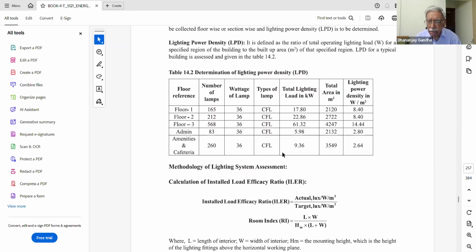The type of lamp is mentioned here for the purpose of our understanding. These are all considered as CFL, compact fluorescent lamps. So the total lighting load is the number of lamps multiplied by 36 watts. For floor 1, 165 multiplied by 36 is about 5,940 watts, mentioned in kilowatts as 5.94. For floor 2, the total lighting load is 22.86 kilowatts. The third area is floor 3, where the lighting load works out to 61 kilowatts.